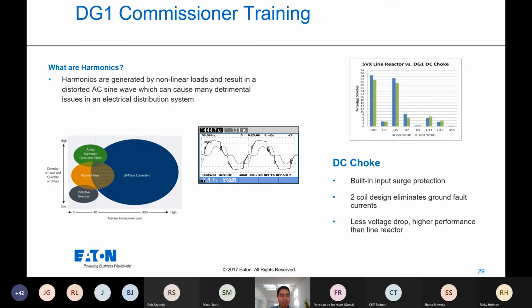So some common filters here are the inductive reactors for the lower horsepower. If you have some budget concerns, passive filters are a great method. And then you also have some other technologies such as 18 pulse converters on the higher horsepower range, active harmonic correction, and there's also matrix technologies which can also help achieve harmonic filtration. And all these harmonic filtration methods will give you different results.